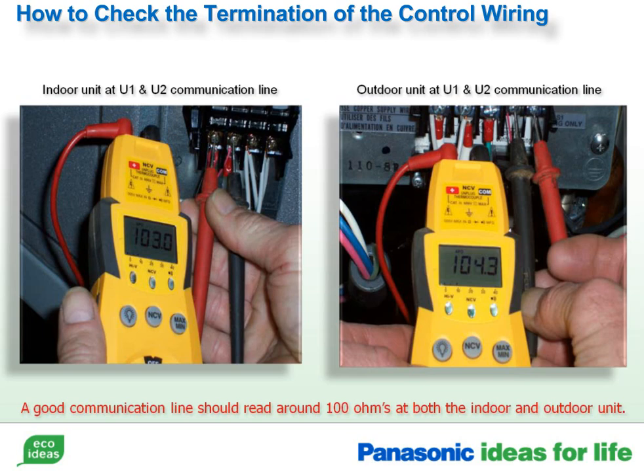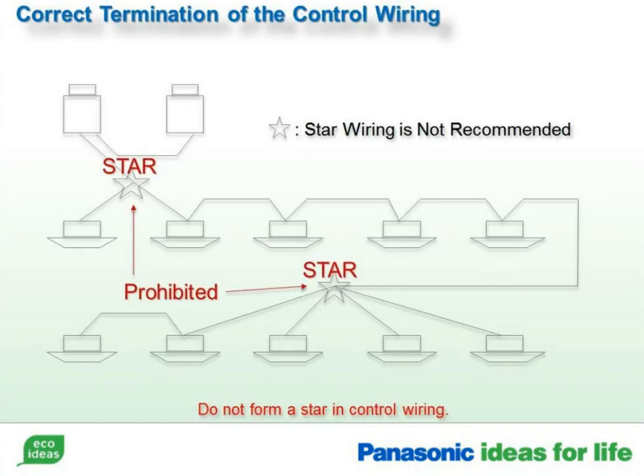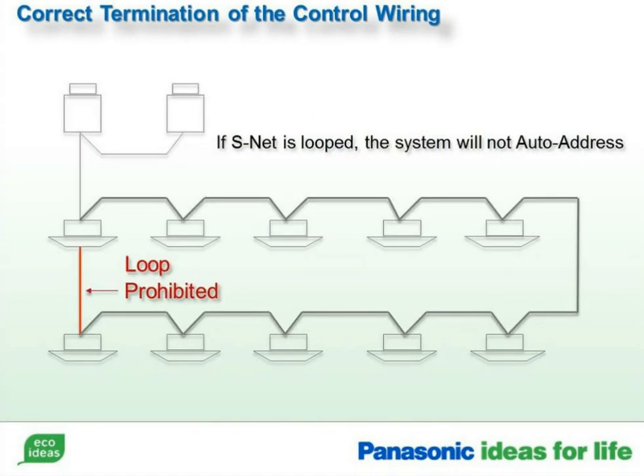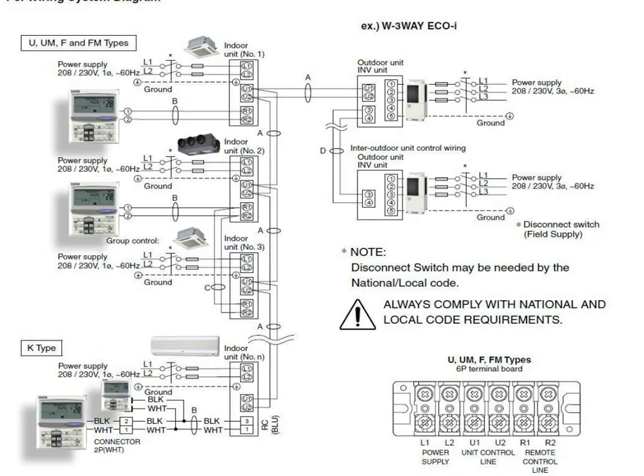This will not help determine if the power is off to an indoor unit, or if the control wires are landed properly. The use of star wiring is not permitted and should never be employed when installing ECOi equipment. Do not loop the S-net control wiring. If you were to make this mistake, the system would never be able to address. Here is another example showing the control wiring for a typical system.